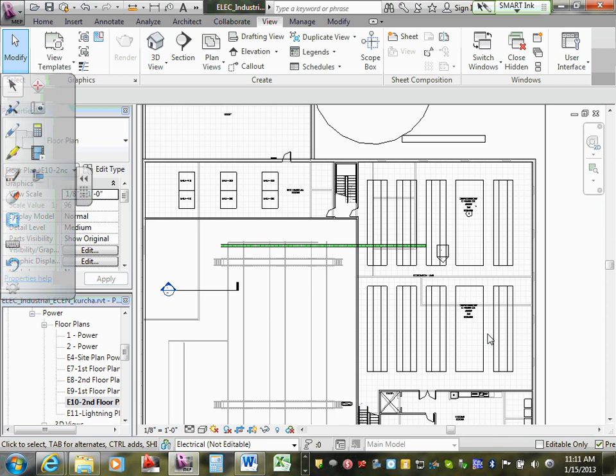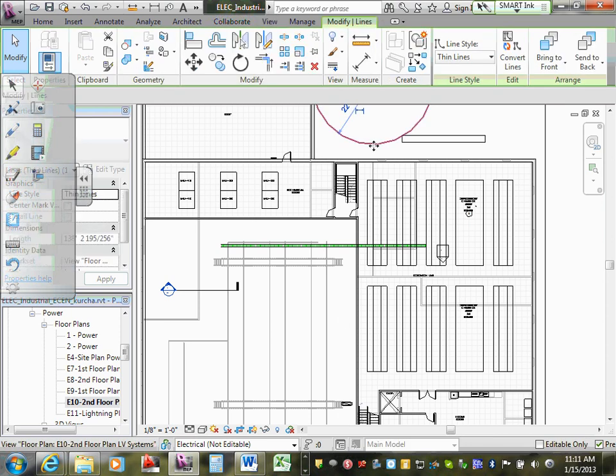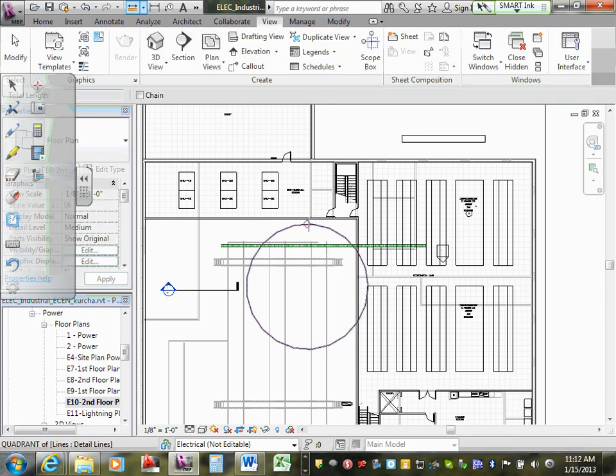We have the .7 rule you can use, but I just like 30 feet. The .7 rule mostly applies to elevator lobbies. Instead of going 30 feet on center, 900 square feet, you can increase it up to, I believe, 41 feet. 44, is that what we use, the 20 foot radius? 41 feet. So you can go 41 feet between detectors in an elevator lobby area instead of the 30 foot spacing. It's basically multiplying it.